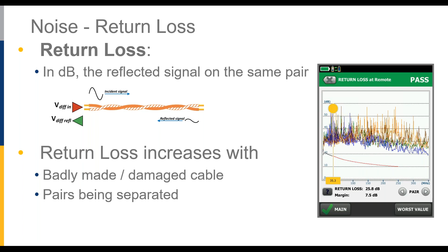And our fun one for our industrial environment here is getting water in the cable. This is actually what return loss is going to look like if you have water in the cable. Now, this doesn't necessarily mean that it's a bad cable. It's just not the right cable for this application. There's our M.I.C.E, and I believe it is the C in M.I.C.E for climatic, or perhaps the I for ingress, where if you're getting water in there, you need to use a more robust cable, something that's got a jacket that's more waterproof.